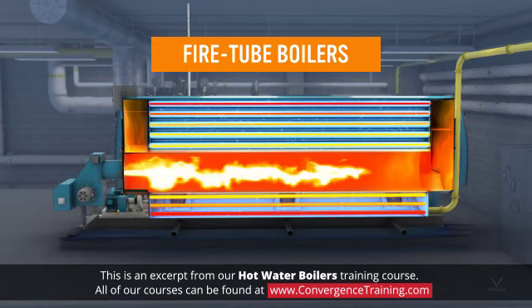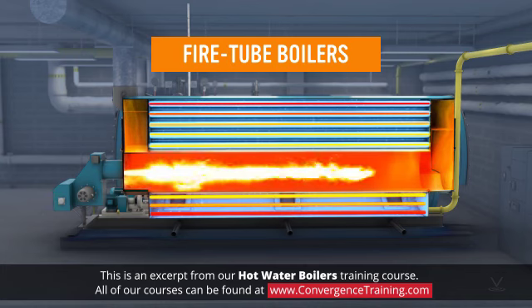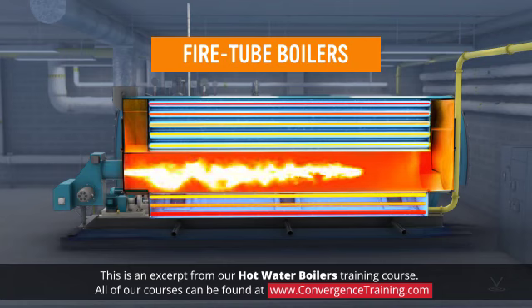Fire tube hot water boilers rely on hot combustion gases passing through a series of metal tubes that are surrounded by water in a vessel. Heat transfers from the hot gases through the tube walls to the surrounding water.